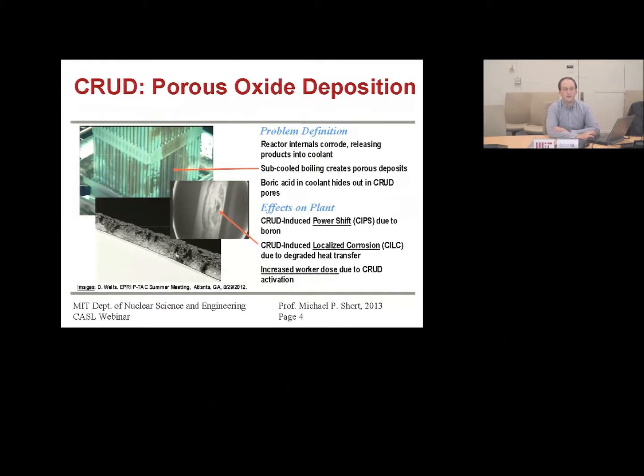The way this stuff works is capillary action will cause water, which contains whatever else is in it, like boric acid, lithium hydroxide and such, to get sucked into the nanoscale pores of the CRUD. And the cladding underneath is quite hot from the fuel.